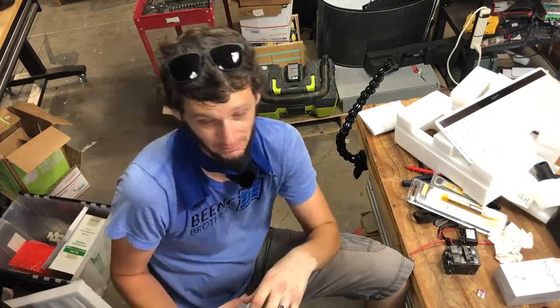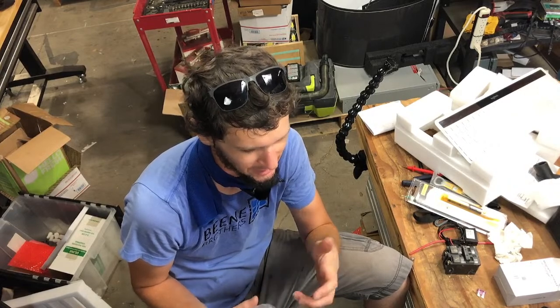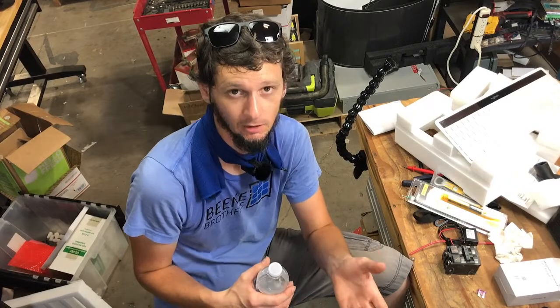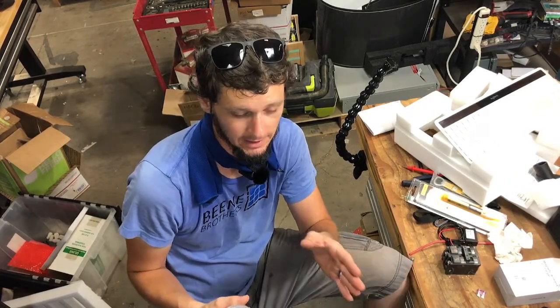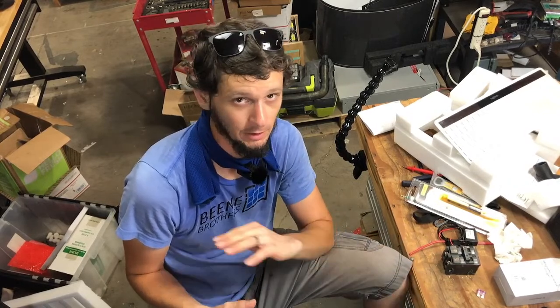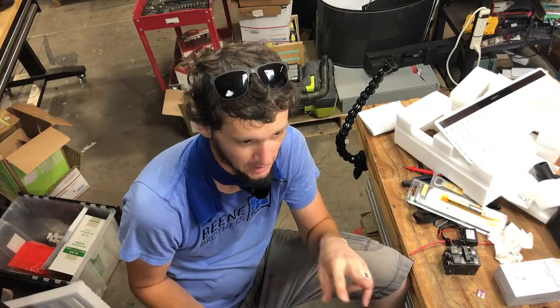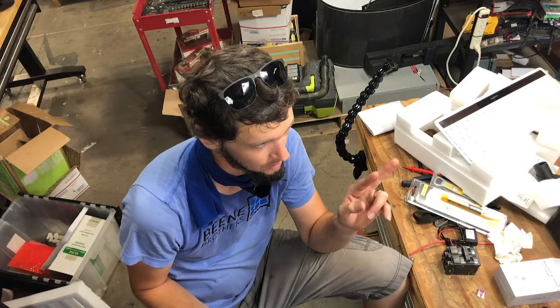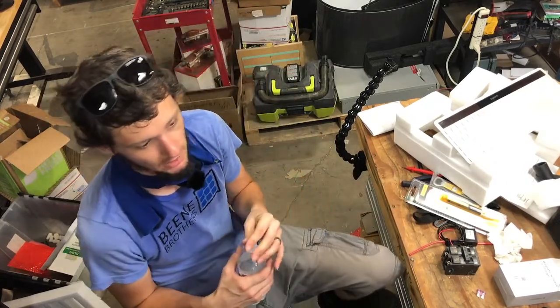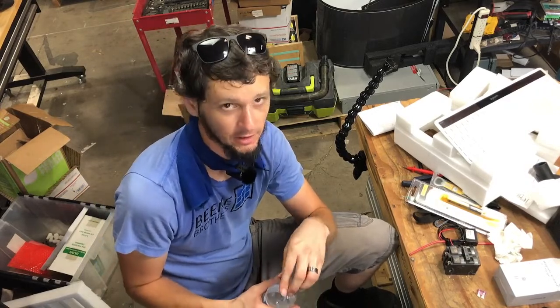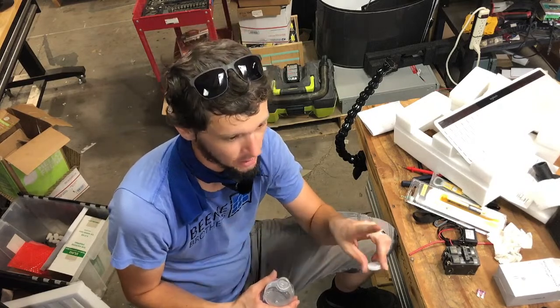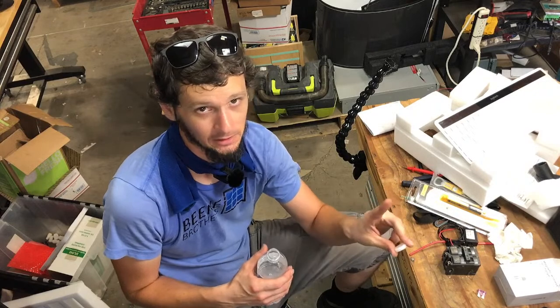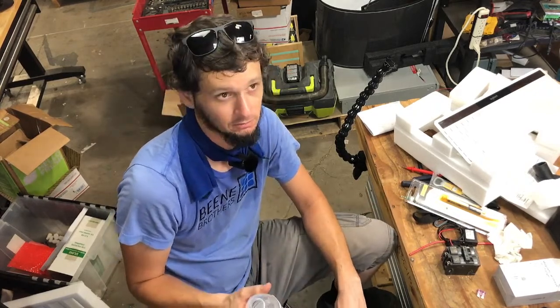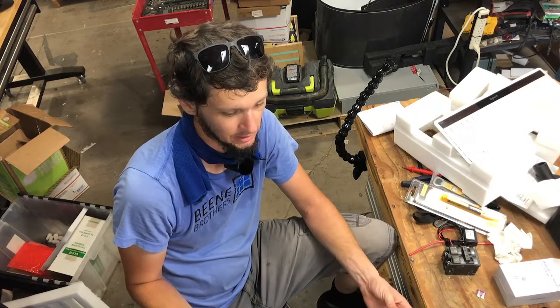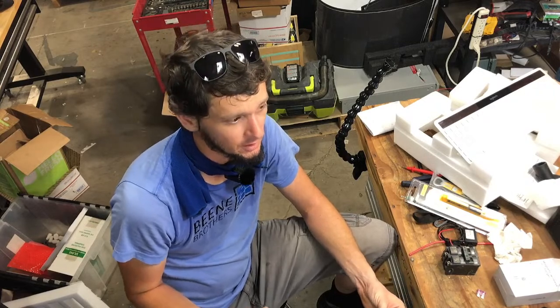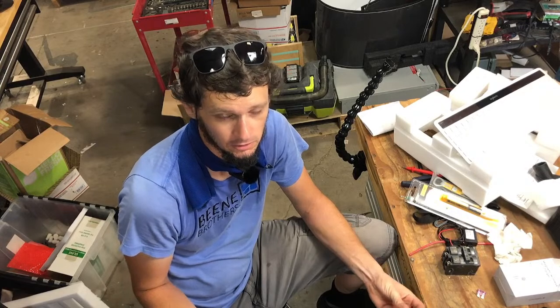For grounding, it doesn't really matter because you're not grounding the negative of the solar array. That negative and the positive coming from the solar panels are floating. They should never be grounded out. The negative and positive go straight into a disconnect and into the inverter charger or charge controller. You should not short that negative to ground. You'll see that a lot in charge controller or inverter charger manuals, they say do not short negative to ground. Negative and ground are not the same thing like they are in a car. Really a car isn't grounded if you think about it, because negative is the body of the car. Maybe that's why they do that, so that's always the negative. But it's not grounded because it's up on rubber tires, there's no ground.